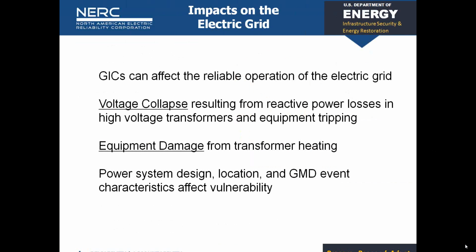We do know that the two primary risks to the grid are voltage collapse and equipment damage. Voltage collapse occurs when the GIC currents John talked about flow in the transmission lines and into the transformer, creating reactive power drag on the system. There's also production of harmonic currents from the transformer caused by the GIC flow in the neutral, a phenomenon known as half-cycle saturation, which produces harmonic currents throughout the system. These harmonic currents can cause relays and protective equipment to trip or operate in an unexpected manner. Both of those things can lead to voltage collapse, and there's also the potential for equipment damage.